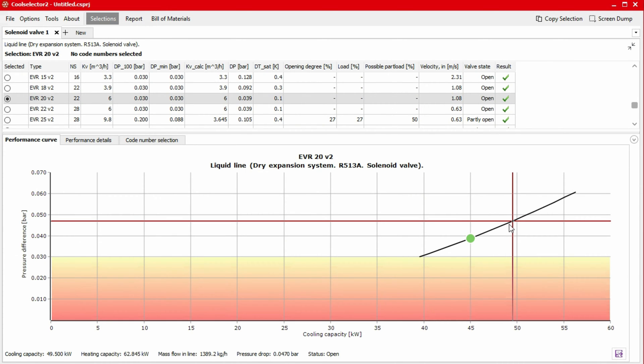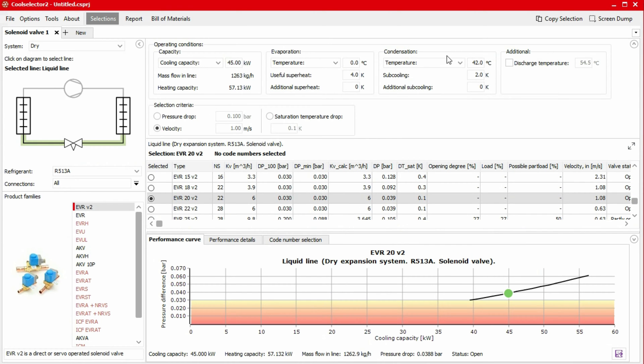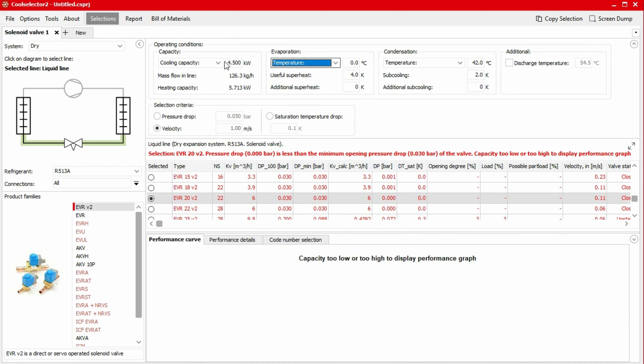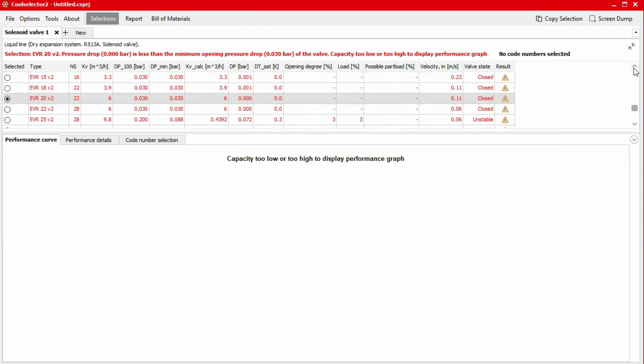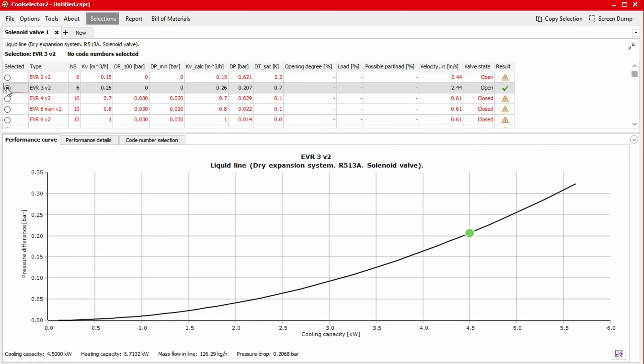For example, in the EVR v2 family, there are three types of valves. If we change our cooling capacity to 4.5 kilowatts, we see the performance curve for the revised suggested solenoid valve has no lower limit. This is because this is the direct solenoid valve which can open and close completely, regardless of the capacity.